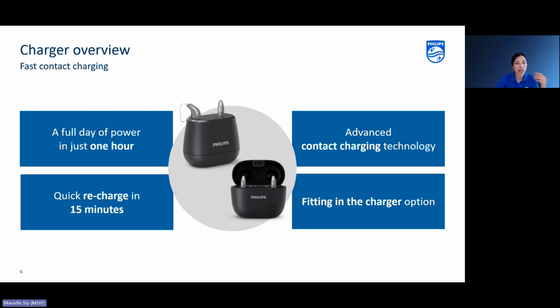The first thing is contact charging provides a full day of power in just 1 hour. When we say a full day of power, we mean 16 hours. If you want to charge it further up to 20 hours, then you would need 2 hours. But if you need a quick recharge, you can easily get 4 hours just by charging it for 15 minutes. So that's really good.